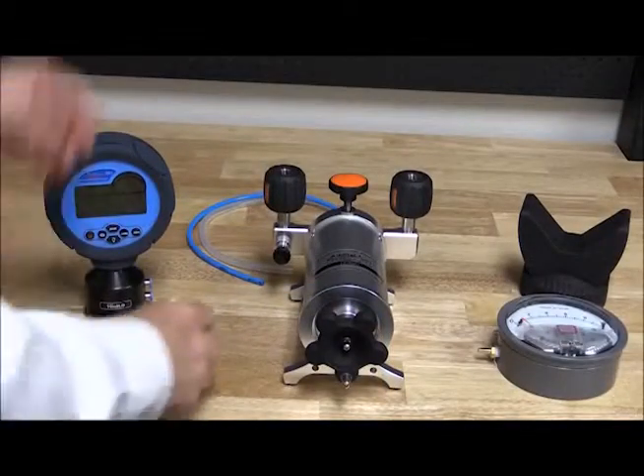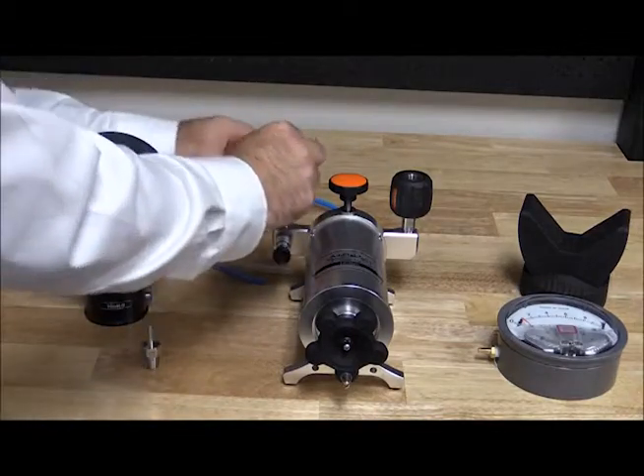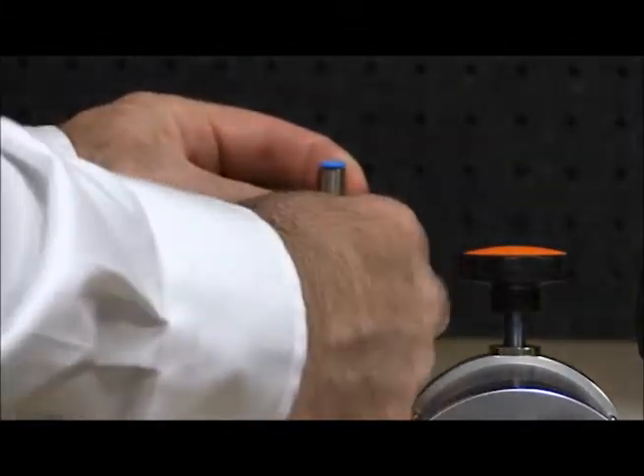For this method, we will connect the high ports for both the reference and the device under test to the 901 pump, leaving both low ports open to atmosphere.